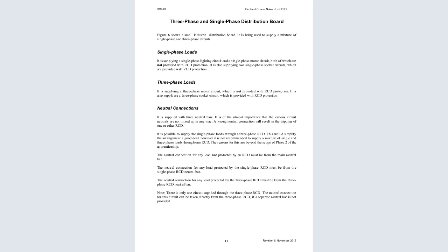It is possible to supply the single-phase loads through a 3-phase RCD, which would simplify the arrangement a good deal. However, it is not recommended to supply a mixture of single and 3-phase loads through the one RCD. The reasons for this are beyond the scope of this video. Now the neutral connection for any load not protected by the RCD must be from the main neutral bar. The neutral connection for any loads protected by the single-phase RCD must be from the single-phase RCD. The neutral connection for any load protected by the 3-phase RCD must be from the 3-phase RCD. So those are the rules of connecting the distribution board.